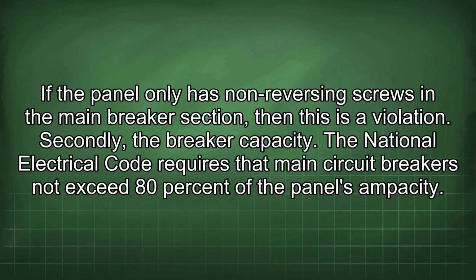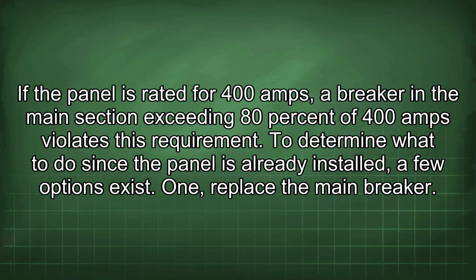Secondly, the breaker capacity. The National Electrical Code requires that main circuit breakers not exceed 80% of the panel's ampacity. If the panel is rated for 400 amps, a breaker in the main section exceeding 80% of 400 amps violates this requirement. To determine what to do since the panel is already installed, a few options exist.